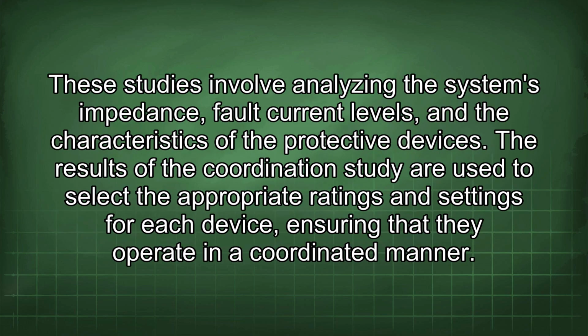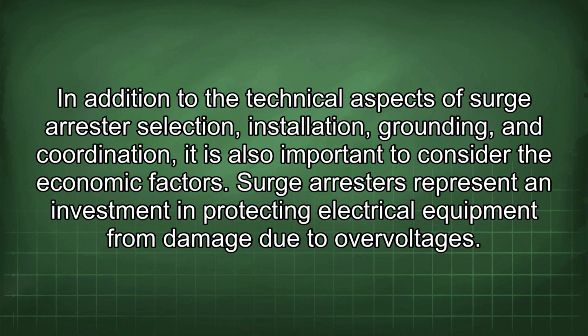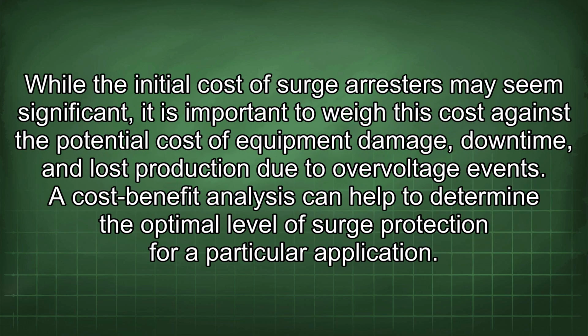These studies involve analyzing the system's impedance, fault current levels, and the characteristics of the protective devices. The results of the coordination study are used to select the appropriate ratings and settings for each device, ensuring that they operate in a coordinated manner. In addition to the technical aspects of surge arrestor selection, installation, grounding, and coordination, it is also important to consider the economic factors. Surge arrestors represent an investment in protecting electrical equipment from damage due to overvoltages. While the initial cost of surge arrestors may seem significant, it is important to weigh this cost against the potential cost of equipment damage, downtime, and lost production due to overvoltage events.